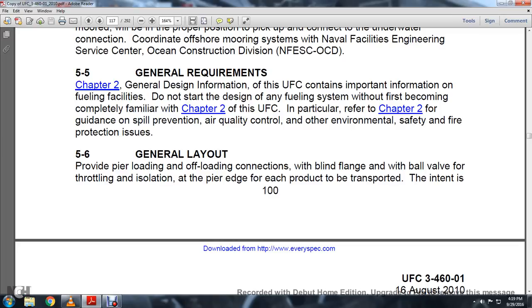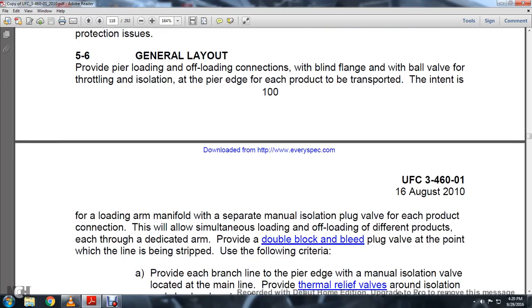5.6, General layout. Provide the pier end loading connections with a blind flange, a ball valve, and throttling isolation at the pier edge for each of the products to be transported. The intent of the loading arm manifold is to have separate manual isolation plug valves with each product connection. This will allow simultaneous loading and offloading of different products, each through a dedicated arm. Provide a double block and bleed plug valve at the point at which the line is to be stripped.